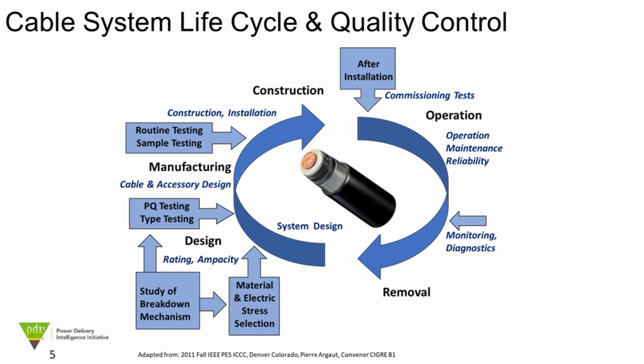There's quality for the stranding processes, and then there's quality for the extrusion process, and measurement of the properties of the material and the performance of the material. Manufacturing uses X-ray machines to look inside the cable, make sure that the dimensions are within the tolerances, and we continue all the way until the final manufacturing process, at which point we do a complete test on the cable. Every single foot of the cable is tested in the factory, tested under high voltage testing, tested for PD, and for jacket integrity.